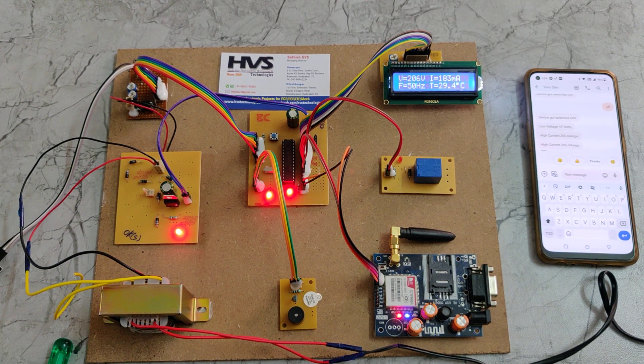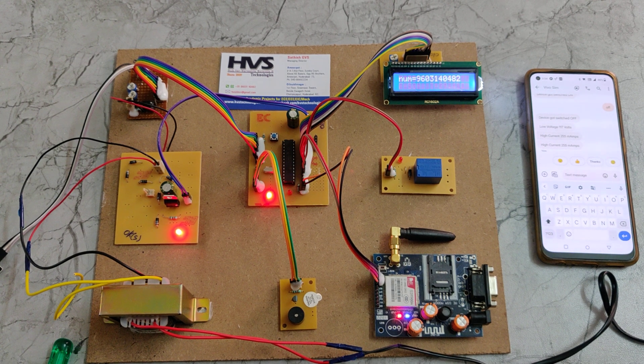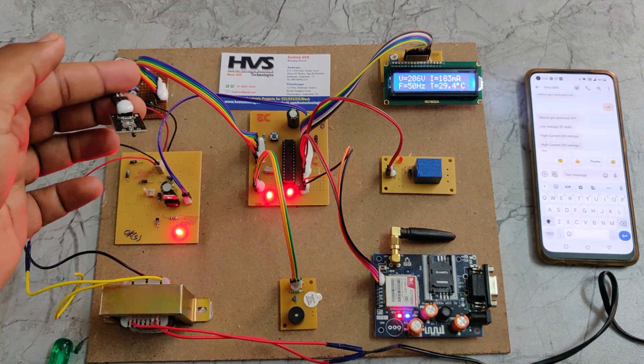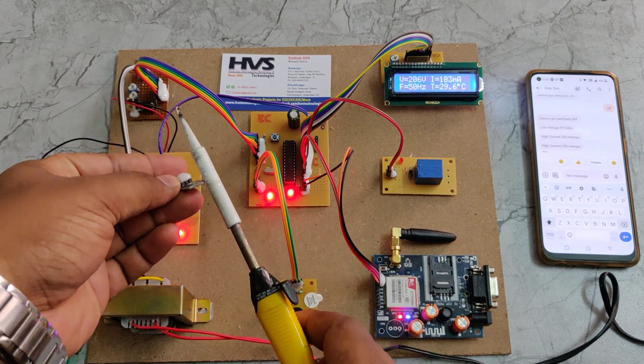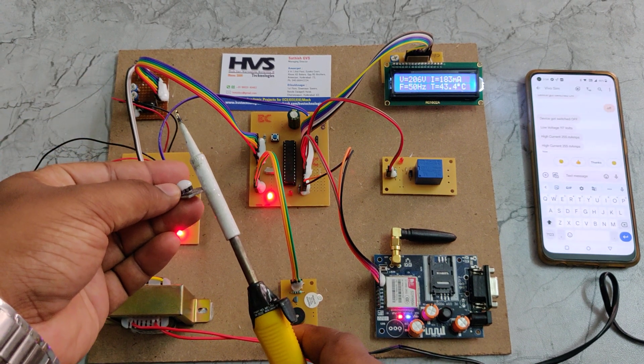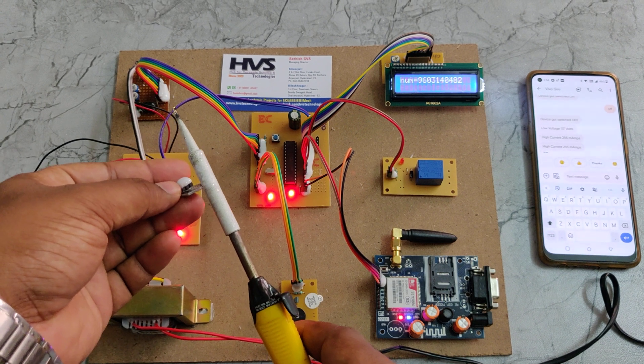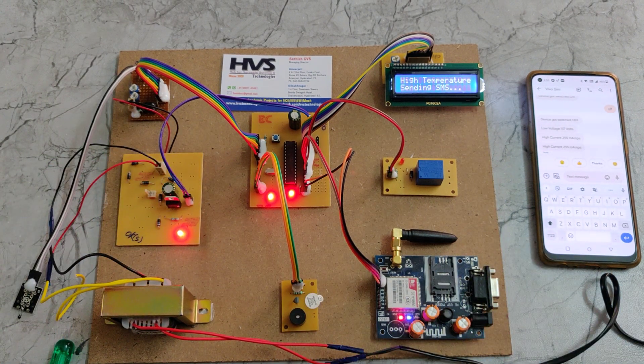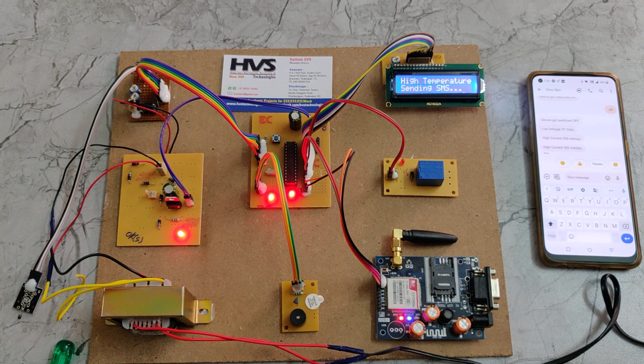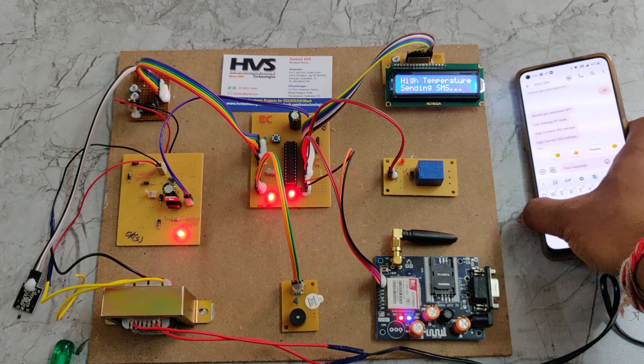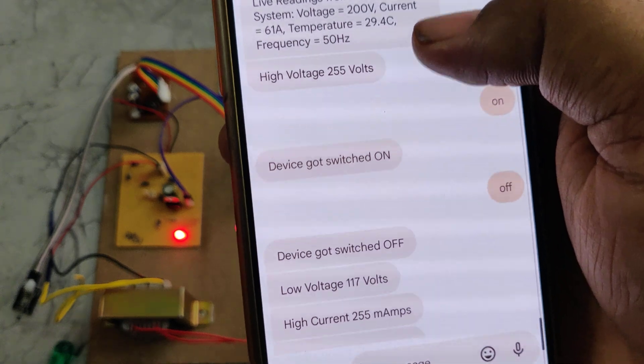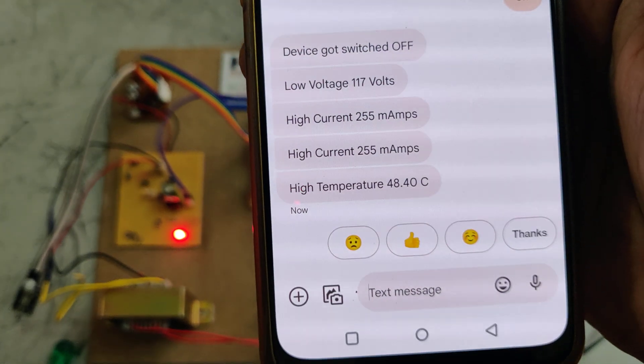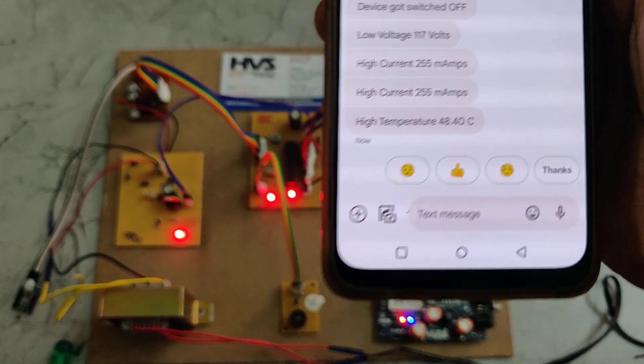Same for the temperature also. When it crosses 45 degrees centigrade, then the system will send the high temperature message alert. Just now we have checked the high voltage, low voltage, high current, and high temperature.